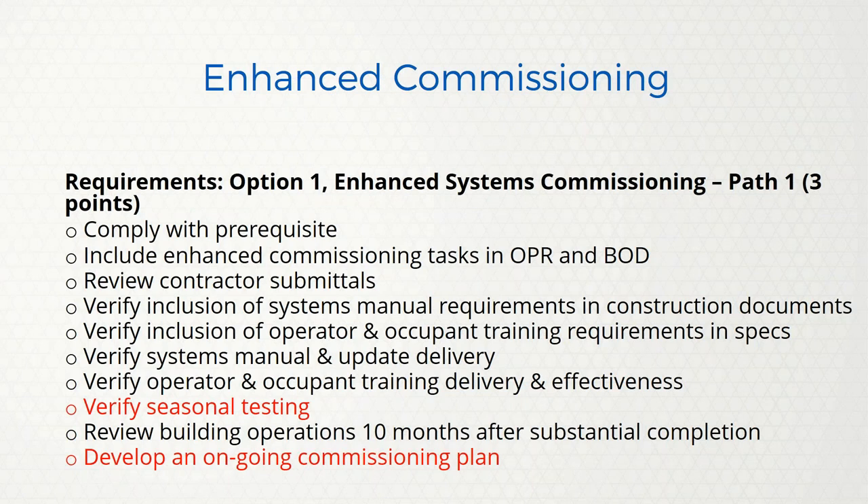In enhanced commissioning there are now several options. Option one, path one, is worth three points and includes mostly the same requirements as original commissioning: OPR and BOD review, reviewing submittals, ensuring system manual requirements are in construction documents, owner operating training. But now we have to verify seasonal testing — if you commission in summer, come back in winter and vice versa. There's also a requirement to develop an ongoing commissioning plan, in addition to the current facilities plan.